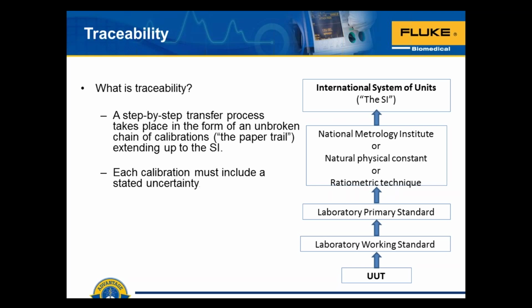So uncertainties, that is, how sure are you that your measurement is within the specified tolerances for that unit of measure as defined by the System International and the BIPM through your National Institute of Metrology in your country. And that's how traceability is gauged. And the unbroken chain means that we can trace every step of the way from our medical device through our test instrument all the way back to SI on the unit of measure that we're talking about.